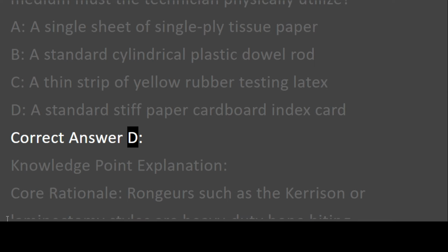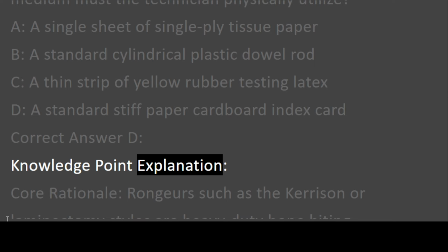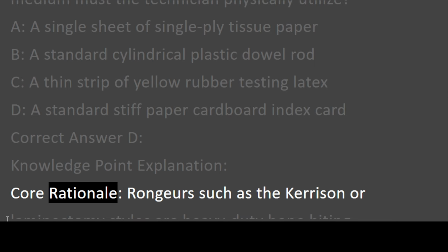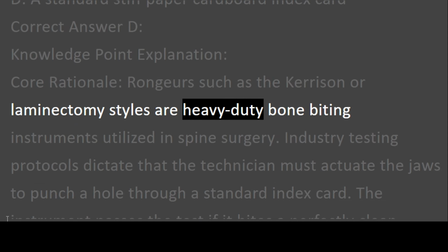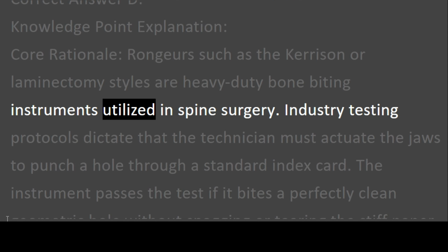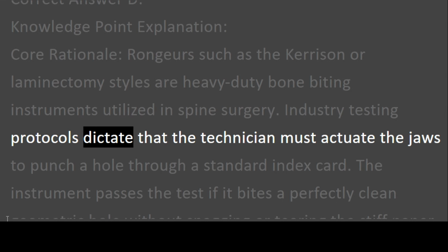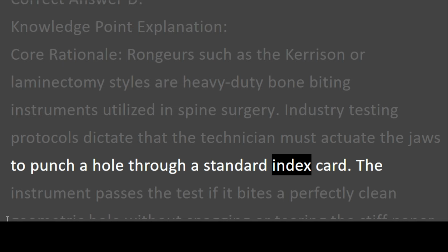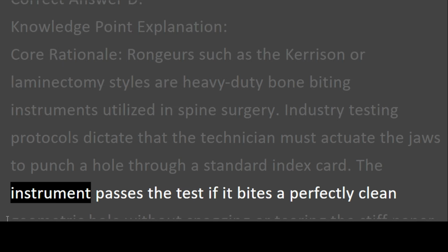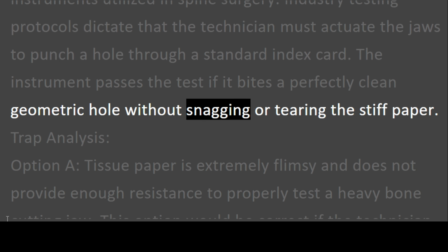Correct answer D. Knowledge point explanation. Core rationale. Rongeurs such as the Kerrison or laminectomy styles are heavy-duty bone-biting instruments utilized in spine surgery. Industry testing protocols dictate that the technician must actuate the jaws to punch a hole through a standard index card. The instrument passes the test if it bites a perfectly clean geometric hole without snagging or tearing the stiff paper.